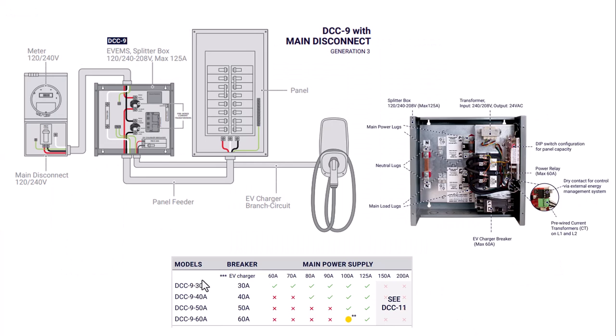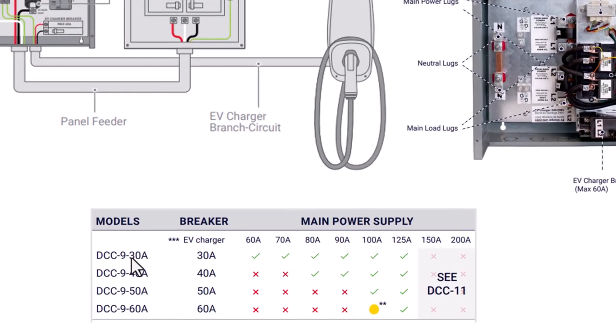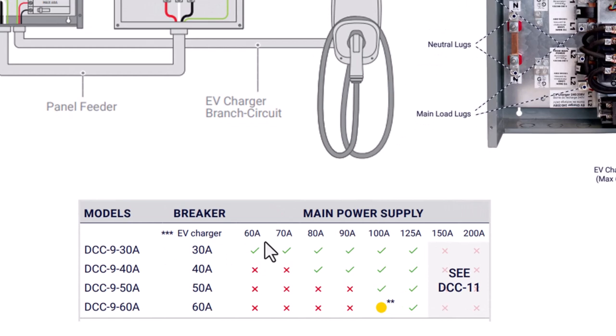And when selecting the model number for the DCC9, you have to select it so that it's a maximum of 50% of the main power supply over current protection device. So if you have an 80, for example, the max has to be 50% of that. So the max has to be 40. So you can see that that is allowed. And you can obviously go a little bit higher because 50% of 100 is 50. And since that's the max, a 40 amp would work.